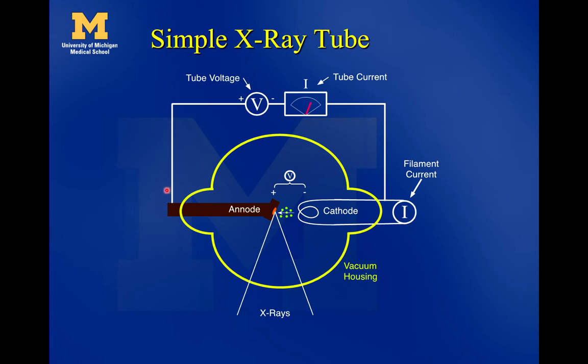Another quantity measured during this is the tube current. As electricity flows from cathode to anode, you have an electrical loop. The tube current is defined as the current of electricity running from the cathode to the anode in the x-ray tube. So we have two different currents: the filament current and the tube current. And that's the basics of an x-ray tube.